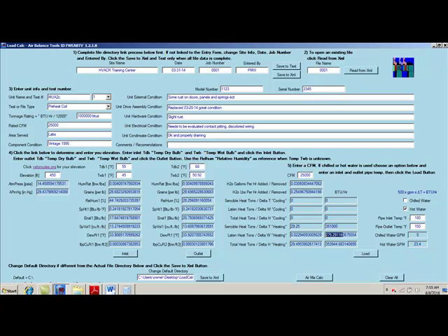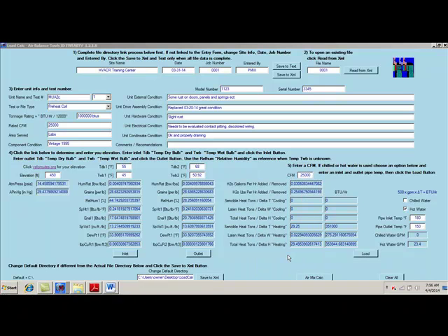The system is so accurate that it will pick up numbers past the hundreds, and we don't have any tools at this point that are typically plus or minus 0.5%, which is a very expensive tool. Most sensors are going to be plus or minus 2%. So in this case, all that matches up.